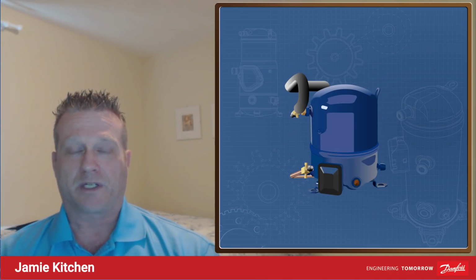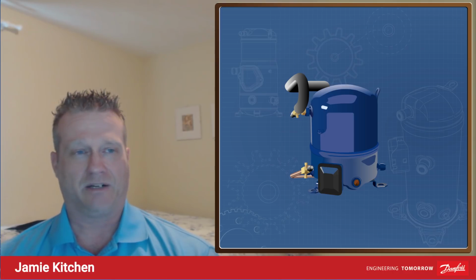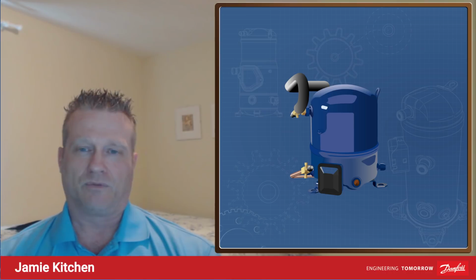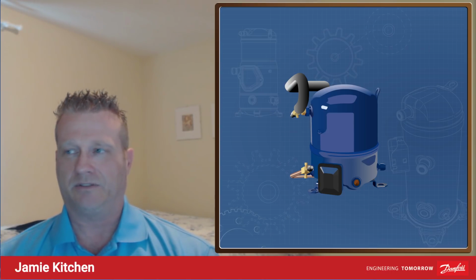Okay, so again, we're not talking about a compressor here, right? But the compressor, unfortunately, is the one left holding the ball when the rest of the system isn't doing what it's supposed to do. Okay, and it takes the fall for it. All right, it doesn't matter if it's a plugged TX valve, a failed fan motor, recirculating the air in the condenser. All these things end up in the same possible way, with a dead compressor or a system that's not going to live nearly as long as it's supposed to live. So don't ignore the rest of that system.